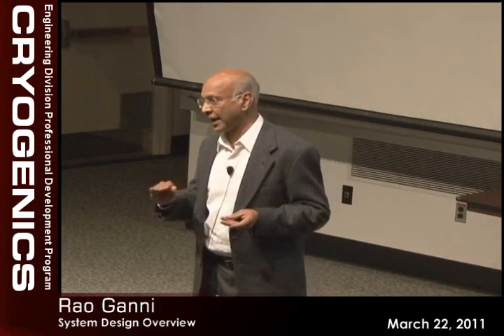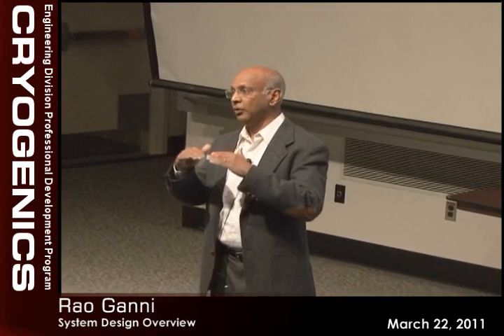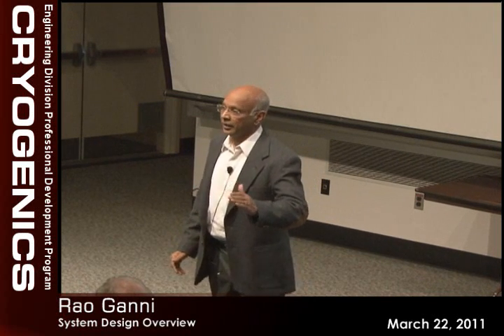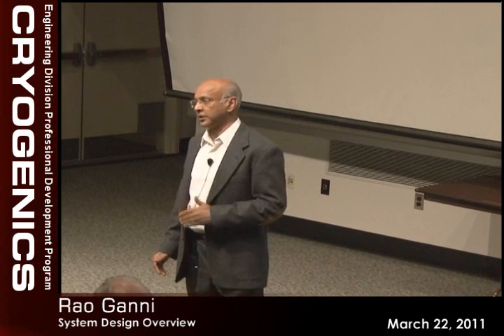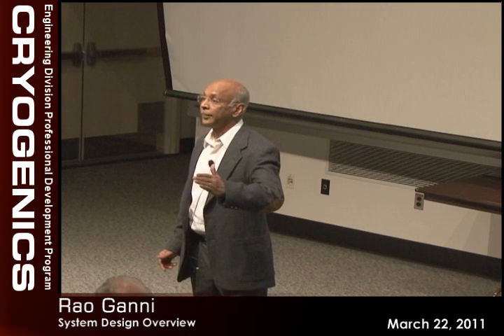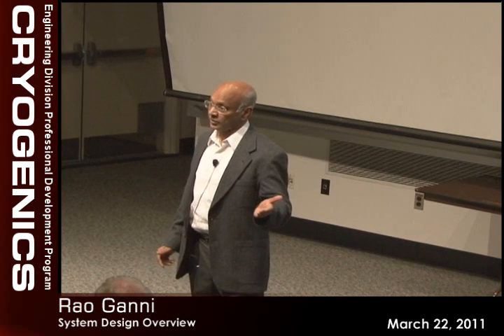I'm not talking about what class or what codes you need to meet. That's a different thing altogether. But in designing the process itself, you have to be aware of these combinations, and not push over certain boundaries of these codes where, by mistake, you end up paying a higher price. You can do a lot better by being on the other side of the border. Between the 150-pound class, up to 20 atmosphere designs, and going to 22, you could have done 20 atmosphere with 10% more mass flow. You would have been a lot better off pushing it to 22 atmosphere at 10% less flow. That's what I'm trying to say.